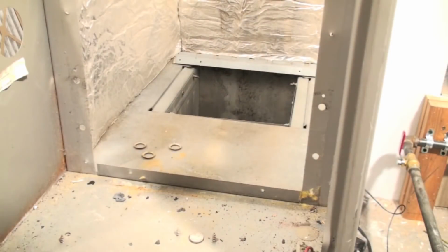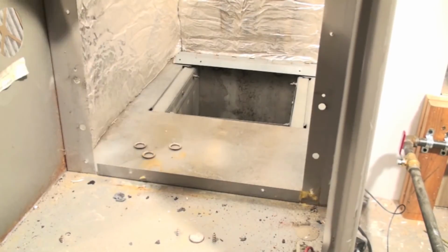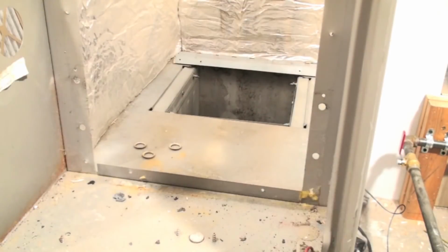I'm going to give you another little trick on how to determine whether these things have a broken heat exchanger, and it's a real simple one. What I would oftentimes do - now I've put those 3 rings laying on that blower shelf right there. The heat exchanger is normally right in here, and a lot of times they'll drop right there on that blower shelf. Sometimes they drop into the blower behind it, but they commonly drop to there.